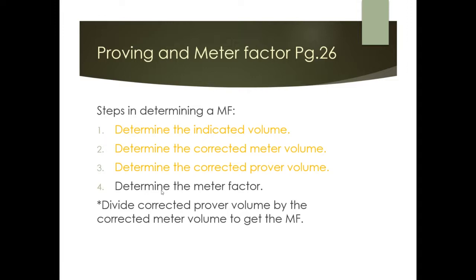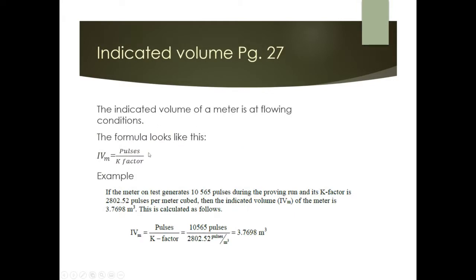To determine the indicated volume of the meter: indicated volume = number of pulses ÷ K-factor. Example: if the meter generates 10,565 pulses during a proving run and its K-factor is 2802.52 pulses per cubic meter, then the indicated volume = 10,565 ÷ 2802.52 = 3.7698 m³.